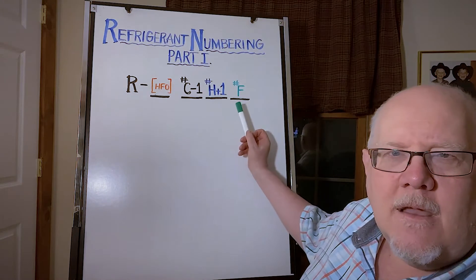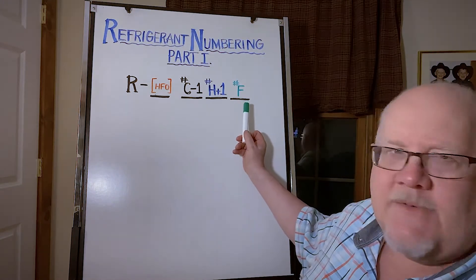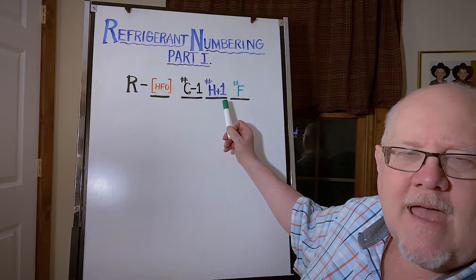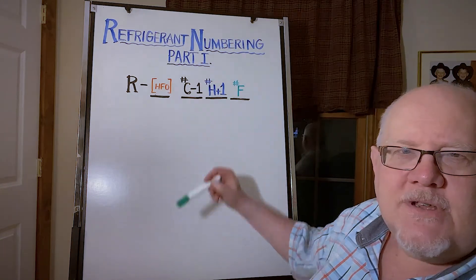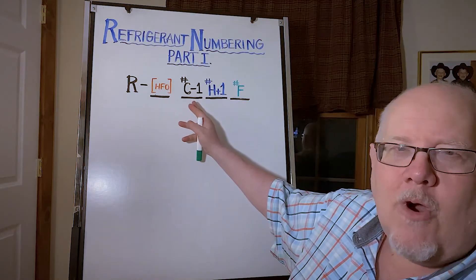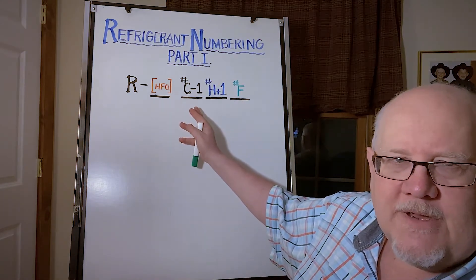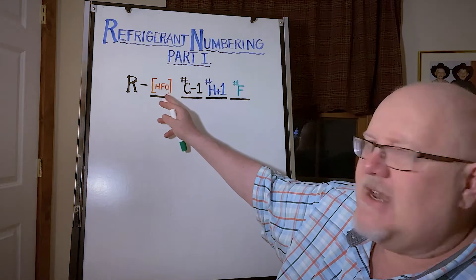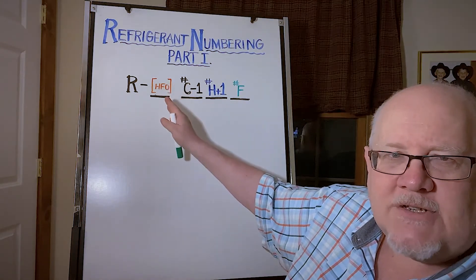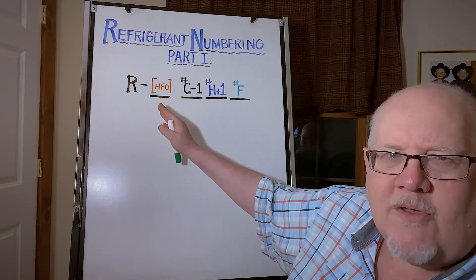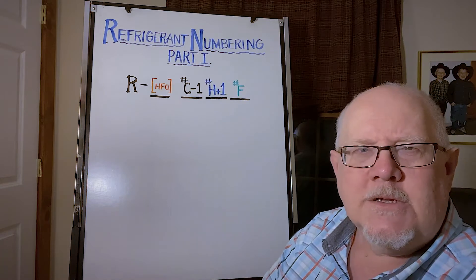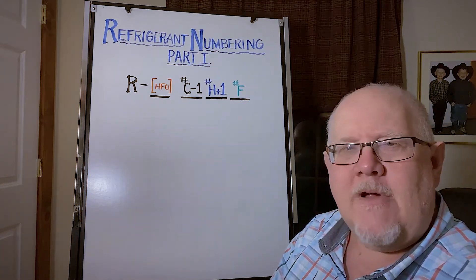So the far right is going to be the number of fluorines. The number next to that, working from right to left, is the number of hydrogen in a molecule plus one. Then we have the number of carbons minus one for the third digit. And then the last digit out here is usually a zero so it doesn't show up, but in the case of an unsaturated olefin or an HFO type molecule, you'll see a one out there in a four digit number.